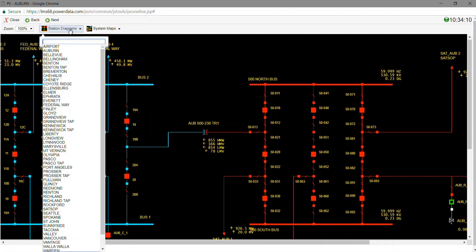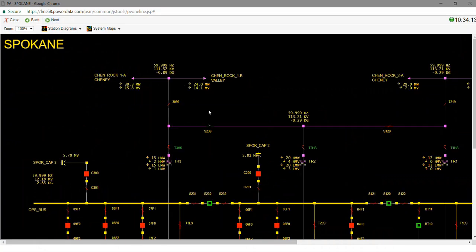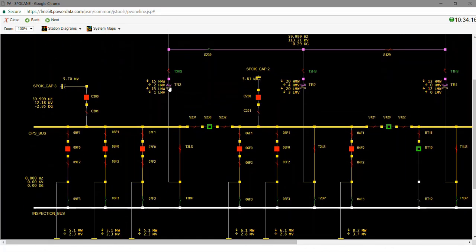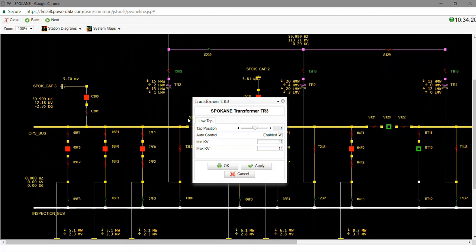Okay, so if we want to check out an example where there is an automatic tap changer, we'll go back to our Spokane station, and I'm going to just click on Transformer 3, and we can see that here I have, first of all, only a low side tap, so it's controlling this 12 kV bus to maintain it. I can see here my auto control is enabled, and it's going to regulate the voltage between 11 and 14 kV. So one thing to remember, it's good to know which transformers have their automatic control enabled. If for some reason I wanted to disable that, I can simply uncheck, and if I hit apply, now it won't regulate automatically. I'll have to keep an eye on that manually.